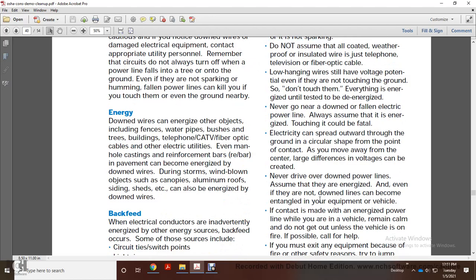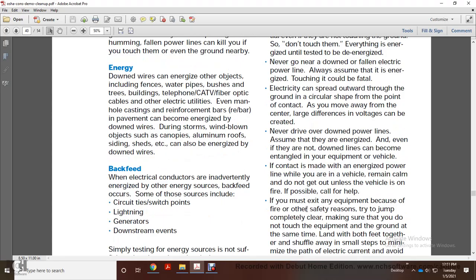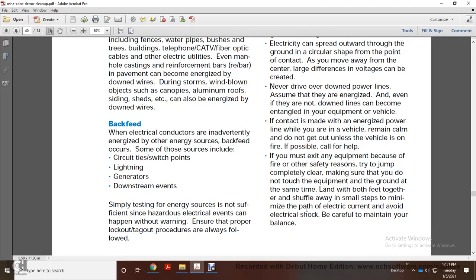Electricity can spread outward through the ground in a circular shape from the point of contact. As you move away from the center, a larger difference in voltage can be created. Never drive over downed power lines. Assume that they are energized, and even if they are not, downed lines can become entangled in your equipment or on your vehicle. If contact is made with an energized power line while you're in your vehicle, remain calm. Do not get out unless the vehicle is on fire. If possible, call for help.